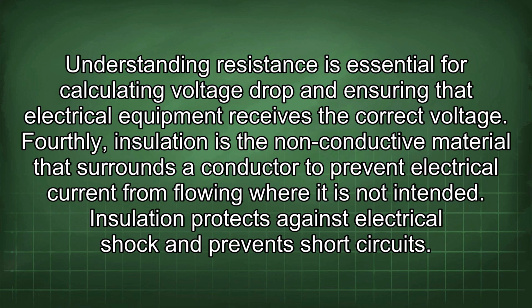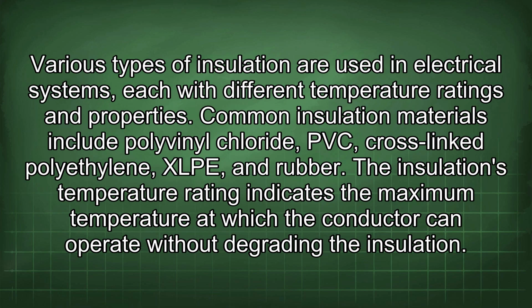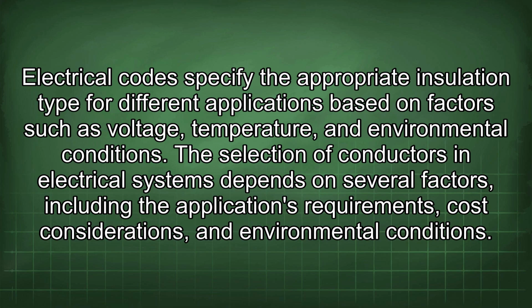Fourthly, insulation is the non-conductive material that surrounds a conductor to prevent electrical current from flowing where it is not intended. Insulation protects against electrical shock and prevents short circuits. Various types of insulation are used in electrical systems, each with different temperature ratings and properties. Common insulation materials include polyvinyl chloride, PVC, cross-linked polyethylene, XLPE, and rubber. The insulation's temperature rating indicates the maximum temperature at which the conductor can operate without degrading the insulation. Electrical codes specify the appropriate insulation type for different applications based on factors such as voltage, temperature, and environmental conditions.